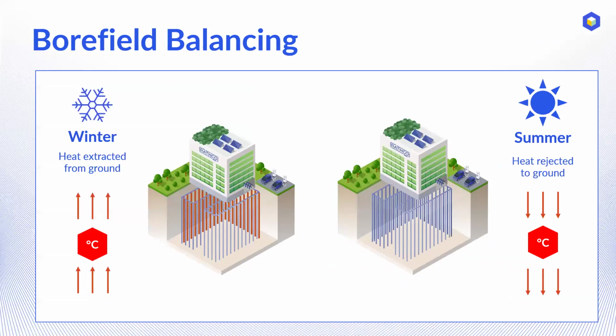So that's what we're essentially doing when we engineer these types of systems - trying to figure out what your building needs with heating, cooling, domestic hot water, all the things that typically use natural gas, and how big we can make the bore field to do as much of those heating loads as possible while maintaining a thermal balance. And then whatever's left over, maybe you need a little bit more cooling, maybe a little bit more heating.